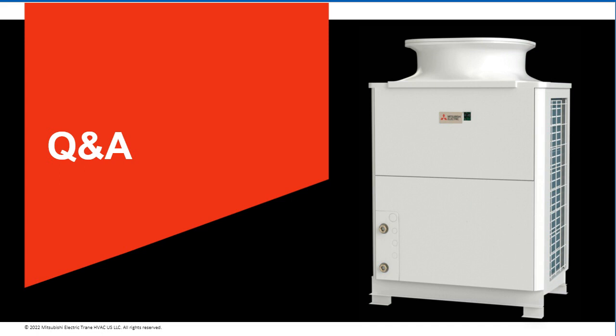Great. How much turn down does the system have? So I'll answer this one. The system does have a variable speed compressor, ECM condenser fan, everything like that, and the turn down is into the single digit or double digit, 10 to 15% overall. But the system actually won't operate like that. It's going to operate more as a storage-based system where it's going to use those inverter compressors and fans as a soft start mechanism. Beyond that, it's going to run at close to 100% load at all times until you get your storage volume up to temp in the tanks, and then it will shut off. So it doesn't act similarly to, say, a VRF condensing unit where it's always modulating to match the load. It's really just trying to build up that hot water temperature in the tanks. And once it's achieved that, it's going to cycle off and wait for the next drawdown through the tanks.